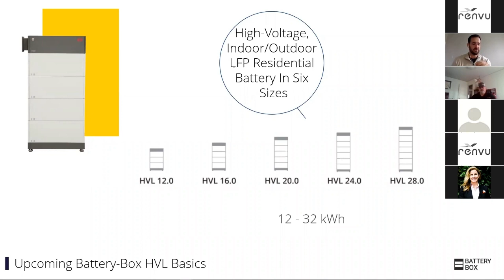Also, when you're creating a battery with a serial connection like this, you need to make sure the voltage and amp hours of each module are identical. So even if they could interact and lock together physically, it wouldn't work from a battery construction, cell design, or serial connection standpoint.